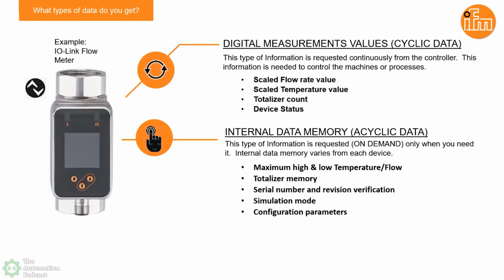In this case, we can send the maximum, high and low temperature and flow that the unit has seen. We don't need to have the PLC have that logic—you can just simply pull this information directly from the sensor.